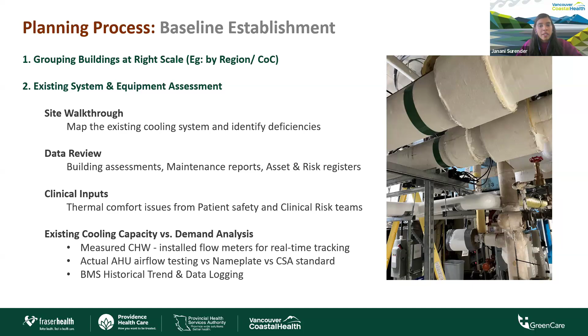Another key part of the process was assessing the system capacity versus peak demand. And to do this, we installed chill water flow meters near the pumps to track the performance during peak summer conditions and identify any stress within the chill water system. We also compared the actual airflow at the AHUs with CSA standards and nameplate readings to ensure that the air system was operating as designed and to find any discrepancies within the air system. And for the buildings that had BMS, we reviewed the trend data and evaluated the system performance over the last 5 years. Next slide, please.